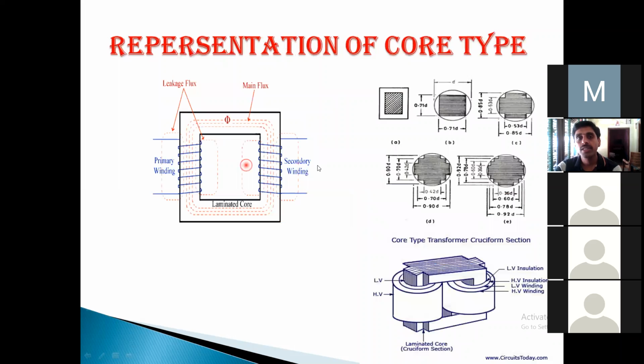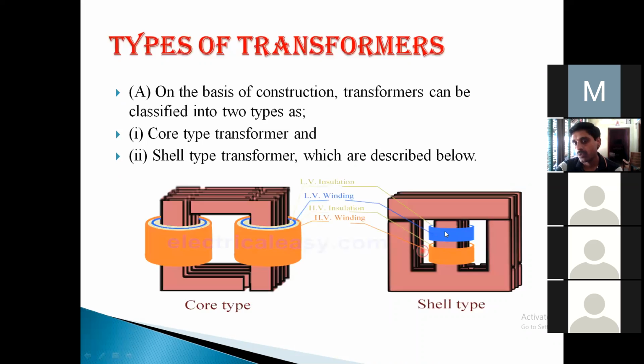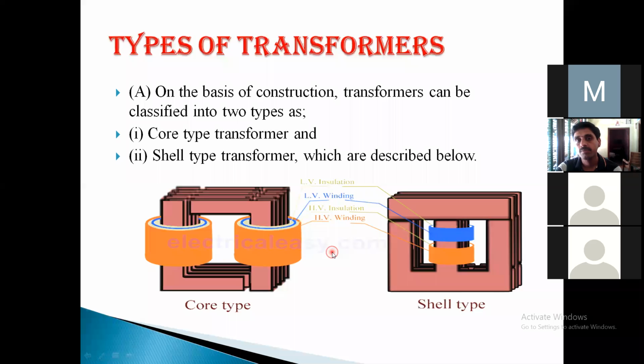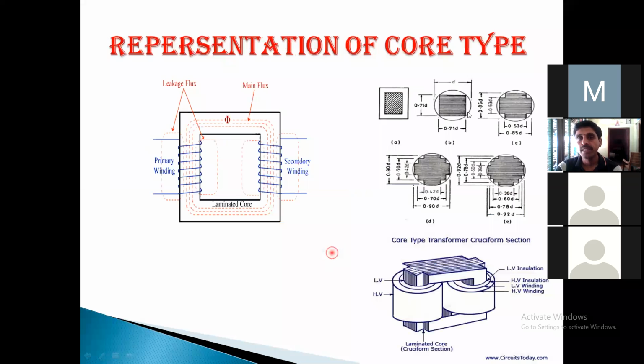So coming to the shell type of transformer, here also, because the core is outside and these windings are kept at the central limb of this one. So representation of the core type of transformers. Normally we'll discuss about the core types of transformers whenever we go for discussion. This is the primary winding, secondary winding, leakage, main flux. And this is the way these construction sections, you can see these laminations, different type of laminations are there. This you can see. This is low voltage winding. This is high voltage winding, like that.